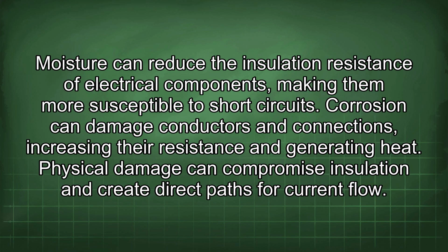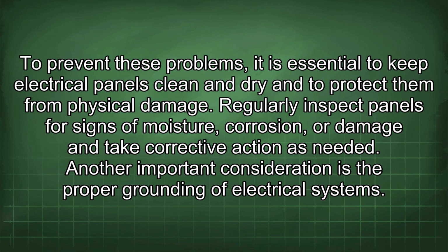Moisture can reduce the insulation resistance of electrical components, making them more susceptible to short circuits. Corrosion can damage conductors and connections, increasing their resistance and generating heat. Physical damage can compromise insulation and create direct paths for current flow. To prevent these problems, it is essential to keep electrical panels clean and dry and to protect them from physical damage. Regularly inspect panels for signs of moisture, corrosion, or damage and take corrective action as needed.